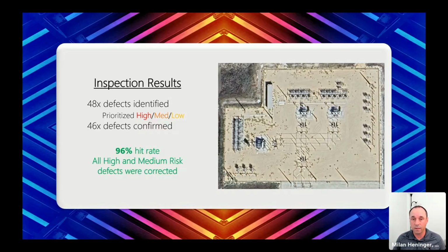The two that they were not able to find were some minor tracking that I had picked up. It had a clear harmonic signature to it. We just went ahead and cleaned those bushings anyway, and we didn't really experience too much later on. I've come to find that in pretty much all substations, some tracking is sort of expected. We want to try to minimize that as much as we can. We need to understand what kind of equipment it's on, but those are things we do see with some regularity.